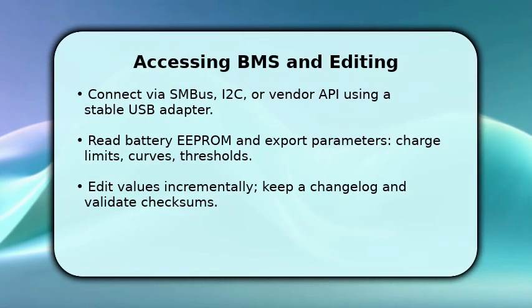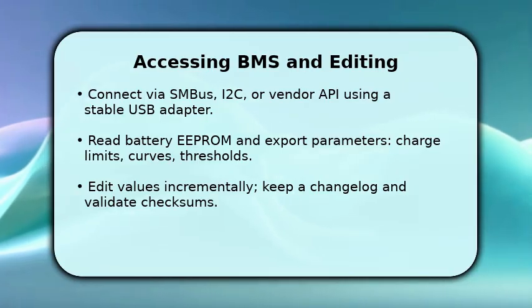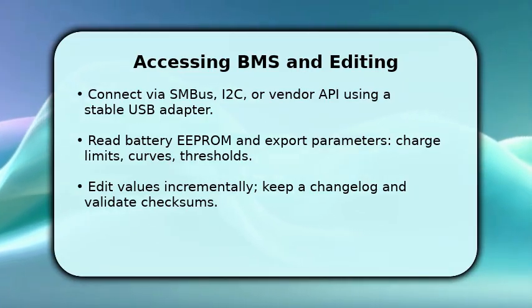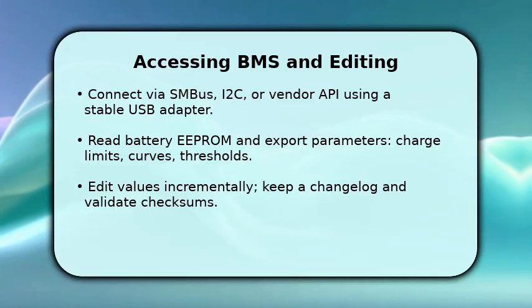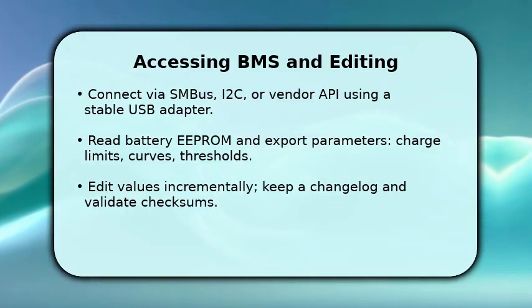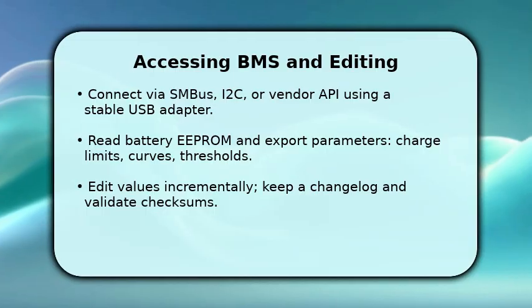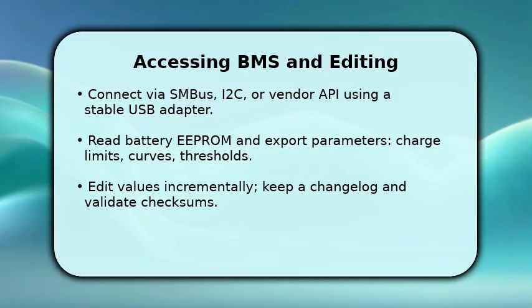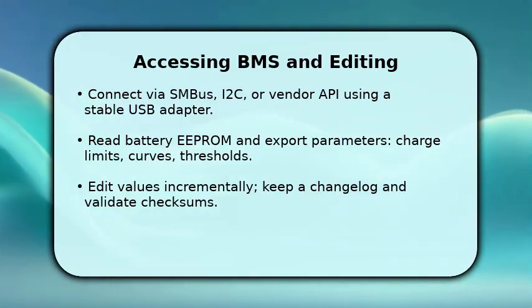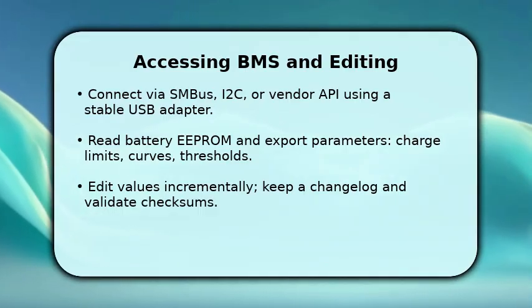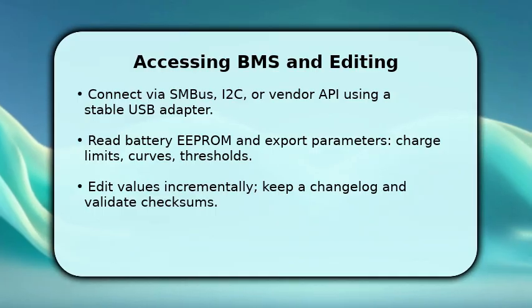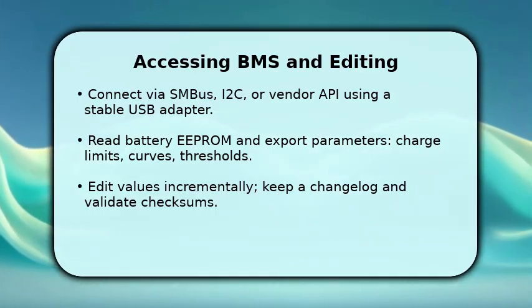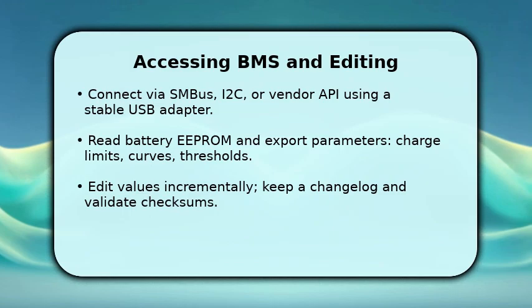You connect to the battery management system using SM Bus or the vendor API and authenticate with the tool because direct access lets you read EEPROM safely. Next, export charge profiles, cell balancing thresholds, and capacity tables. You need these as baseline data. Then edit values in small increments, do not jump values, while keeping a detailed change log and verifying checksums after each write. Once you write a parameter, validate behavior with one test charge-discharge cycle to ensure stability.